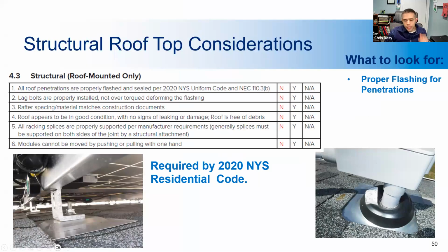All right, so moving on to structural rooftop considerations. The guidebook has a section for rooftop PV attachments and penetrations. In addition to verifying that they're present, you have to verify that they're installed properly. The guidebook gives us examples of the proper installation. You may see flashing that's not installed according to the manufacturer's instructions, things like that. It's important for contractors to follow these guidelines and for inspectors to know what to look for.